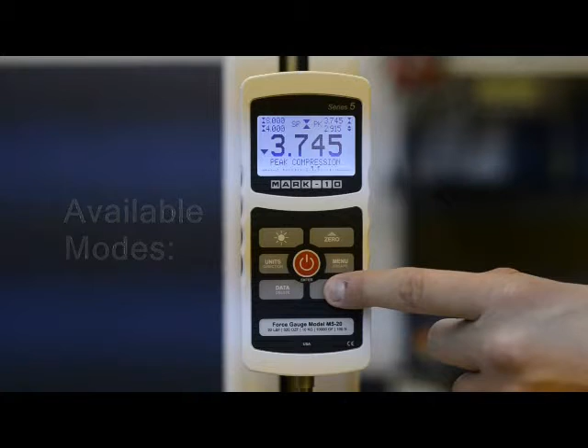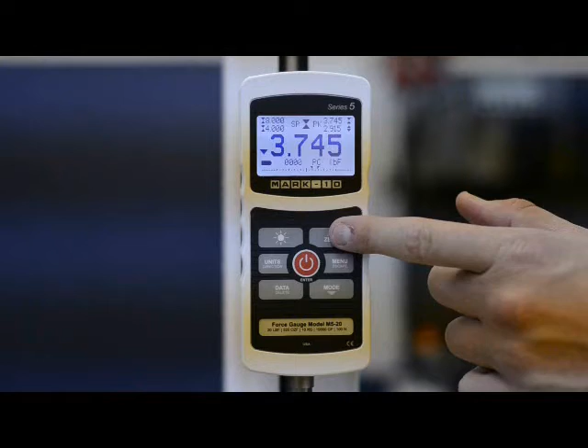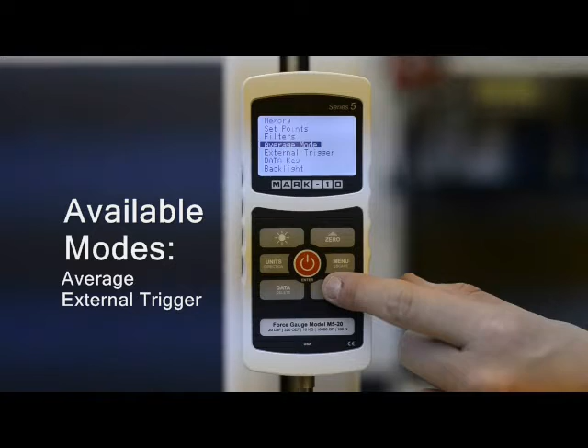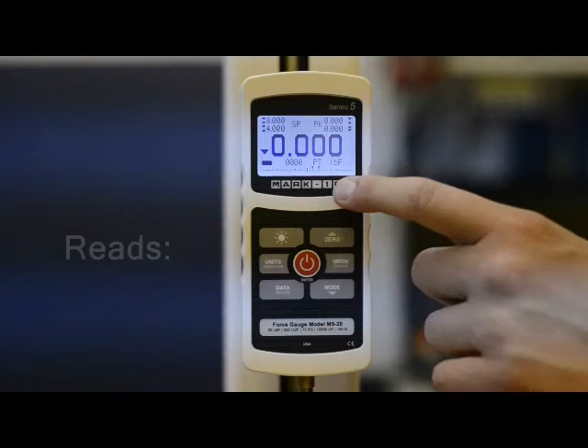As I mentioned, I'm in real-time mode, but I can change that mode to peak compression, which means the screen will be frozen when the peak compression force has been reached. There's average mode, where you can set up the gauge to record the average force over time. External trigger mode is where the display will be frozen when an external trigger has been received, such as a switch contact activation. Currently we're reading in pounds.